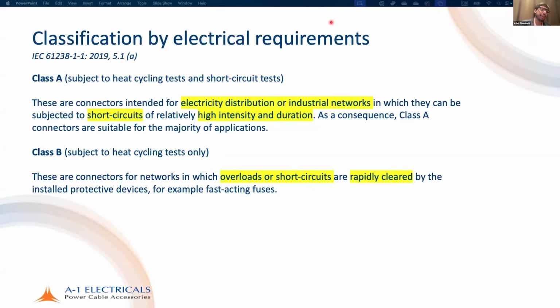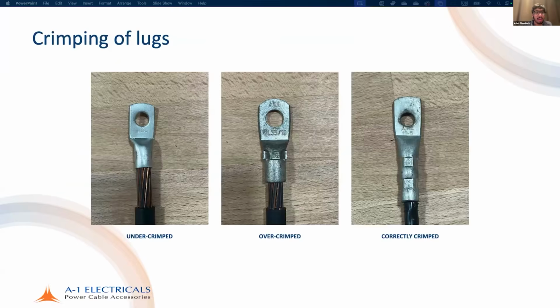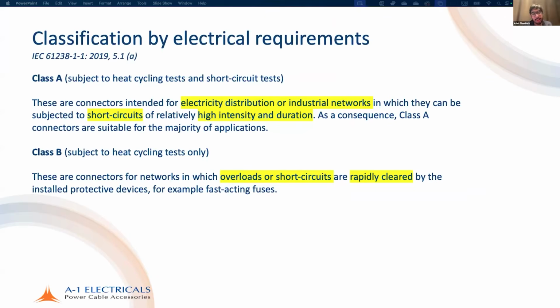Class B is a connector that is subject only to heat cycling tests. So it is a particular connector that is only intended for use where overloads or short circuits are cleared rapidly. As you can imagine, the class A connectors are subject to far more rigorous requirements. And of course, as Mr. Gandhi was telling me, A1's lugs, just as an example, are all class A. So they meet this requirement of high intensity and duration. Oftentimes we just go to the market and buy a lug. We don't really think about whether they are class A, class B, etc.